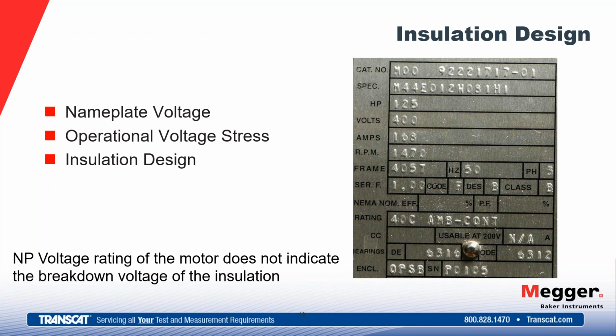So there's several reasons why this is important, but the most important reason here is that the voltage stresses imposed on the winding during contact opening and closing operations can be as high as 4 times the applied bus voltage. So our motors are seeing voltages higher than what we're applying to them by the bus. If motors were only insulated to withstand nameplate voltage, they would fail almost as soon as they were placed into service due to these higher voltages, voltage spikes that occur during breaker opening operations, and if that motor is on a VFD, it's seeing those voltage spikes during normal operation.